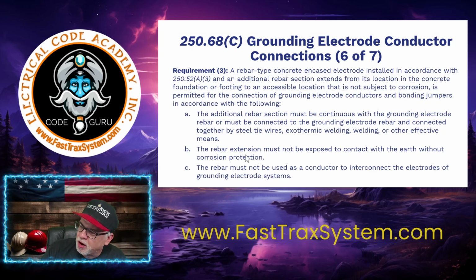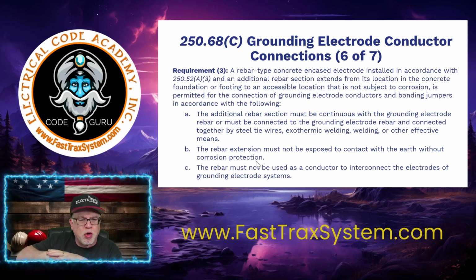Next, the rebar extension. We're at B now. The rebar extension must not be exposed to contact with the earth without corrosion protection. So this extension that comes up is typically going to go down into the encasement and come up into the wall, so it's not going to be exposed to contact with the earth, unless it has some type of corrosion protection. If it's coming out and you make that connection, then it would have to have some type of corrosion protection over top of that connection to protect that rebar and that connection.